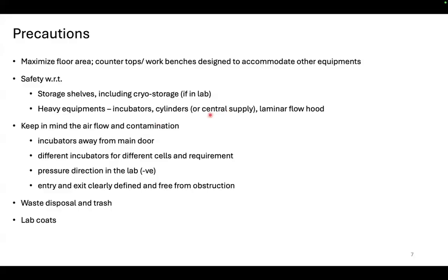But also in some cases, suppose the entire building is dedicated to doing cell culture, then it doesn't make sense that every lab has their own CO2 supply and you keep filling and refilling CO2 cylinders every week or every 2 weeks or whatever the time it takes, right? So instead, you can have a centralized CO2 facility, managed by that department or that building. And then you just need to ensure that your pipes and all are connected fine.